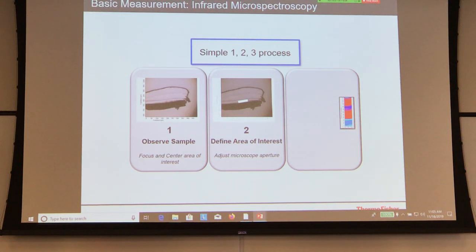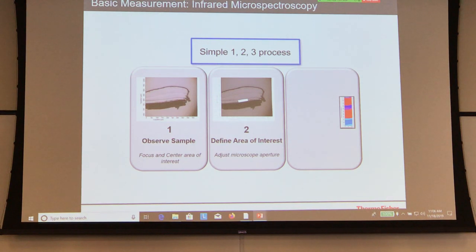Aperturing is important — it's different from focus. An aperture is basically two metal blades that close down the beam of light so it hits just your sample and nothing around it. In the microscope, the IR beam can be around 200 microns when fully focused, but if your region of interest is only 20 microns, you cut the beam down so it only sees that region. With the instrument, you can actually see while you're measuring — you view it, set the aperture, and the visible aperture is visible to you as visible light.